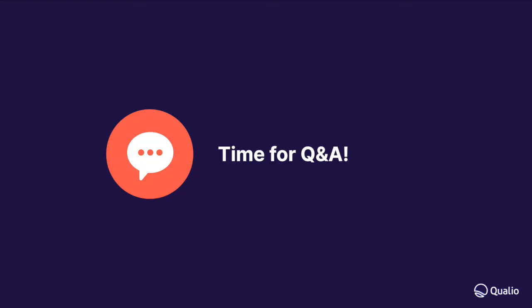Perfect, thank you, Richard. And then in order to use design controls, risk, et cetera, do you have to be using Jira or some other tool, or is there a way that you can just use Qualio natively? You can use Qualio natively, yes. That's one of the examples I was showing. Typically what we're seeing for a lot of device companies is they're using things like Google Docs or just spreadsheets to manage their requirements. Qualio Docs is actually quite a good replacement for that, and gives you dynamic linking between the items to build your hierarchy just using Qualio.